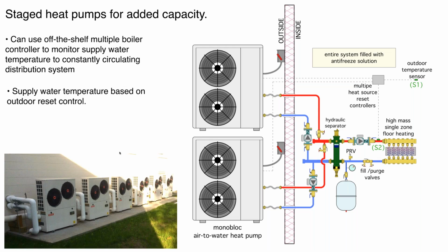So the lower left, that actually is a facility down in Massachusetts with 6. And I believe those are each 5-ton units. And I do know of some projects that have done this. And again, the limitation here could be single phase power versus going with a larger heat pump. And you also have capacity control. So with 6 heat pumps, you would have 6 stages of heat input. So the controller could better match the heat pump output with the load. And again, minimizing the need for any kind of thermal storage in the system as far as the buffer tank.